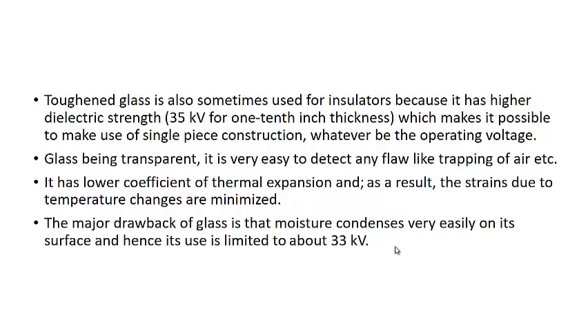Toughened glass also is sometimes used for the insulator because of its high dielectric strength, which is 35 kV for 1/10th of the inch thickness, which makes it possible to make use of a single piece construction, whatever may be the operating voltage, because you can see that its dielectric strength is twice that of the porcelain. Glass being transparent, it is very easy to detect any flaw like trapping of air, or some cracks or other things. It has a lower coefficient of thermal expansion. That means when temperature increases, it will not expand so much as compared to porcelain. Therefore, the strains due to temperature change are minimized.